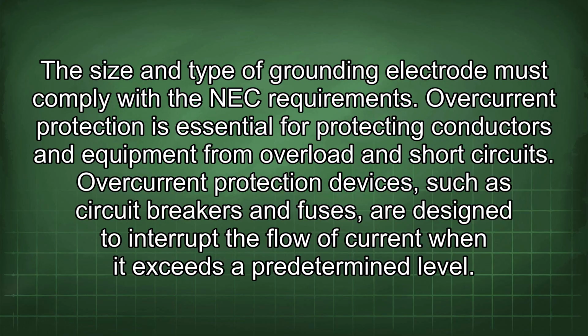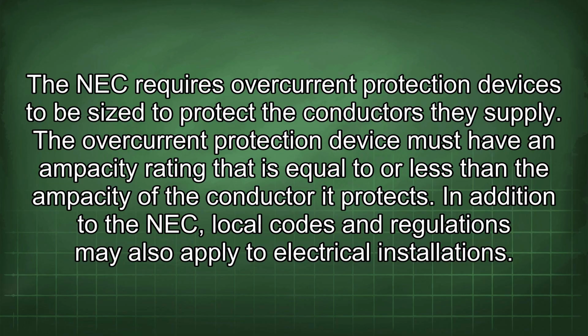Overcurrent protection is essential for protecting conductors and equipment from overload and short circuits. Overcurrent protection devices, such as circuit breakers and fuses, are designed to interrupt the flow of current when it exceeds a predetermined level. The NEC requires overcurrent protection devices to be sized to protect the conductors they supply.